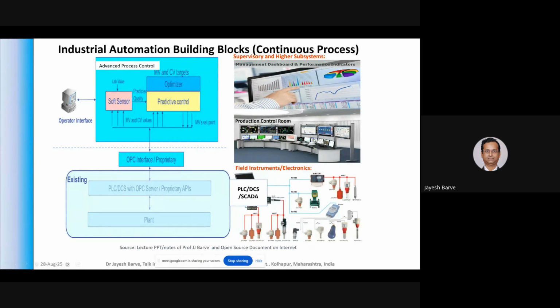Now, this is the control room for that. But now what is happening? Your field instruments - here, field communication is a different protocol. It's called the operational layer, operational communication protocol. So field bus, Profibus, signals 4 to 20 milliampere, or digital RS485 based bus, having Modbus protocol or Profibus or CAN bus protocol. All these different protocols are called the industrial protocol or operational protocol for the control system.